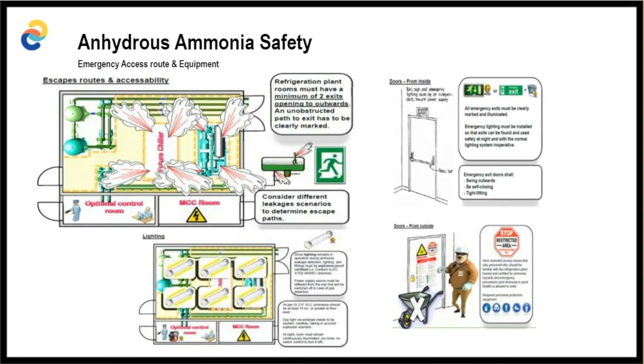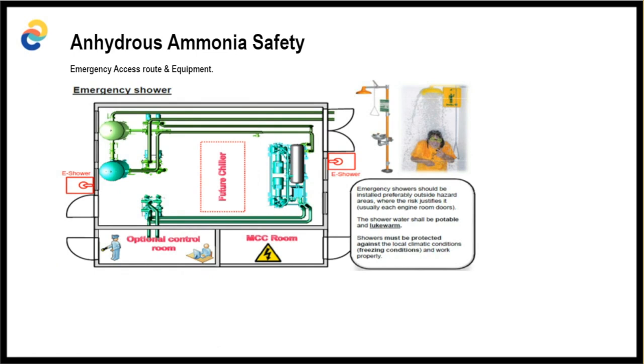Okay, so for this slide, all equipment shall be located in such a manner as to allow enough space to exit in the event of an emergency. Emergency exits must be clearly marked and illuminated. No obstruction should be located in these exits. Also, based on the code, the machinery room shall be equipped with light fixtures delivering a minimum of 320 lumens per square meter. Okay. Another best practice is that each machinery room shall have access to a minimum of 2 eyewash or safety shower units.